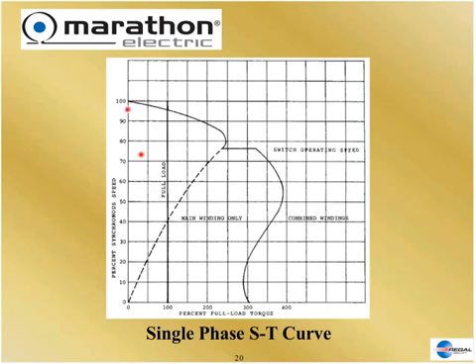Here's the speed-torque curve of the motor with only one winding: it goes all the way down to zero speed and zero torque — it will not start. The auxiliary winding, placed strategically in the motor, causes the wave to get off dead center. It gets started, accelerates up, goes through a switch point, and then can continue to run. Once we get it started, it will run.